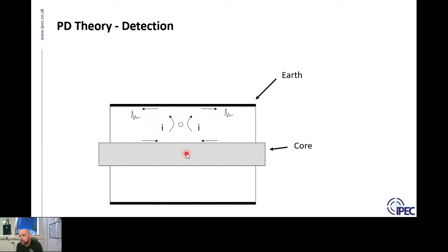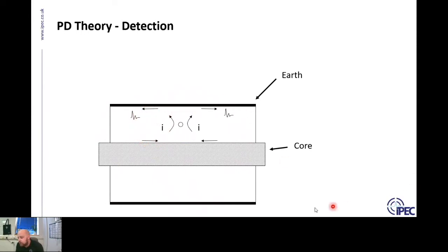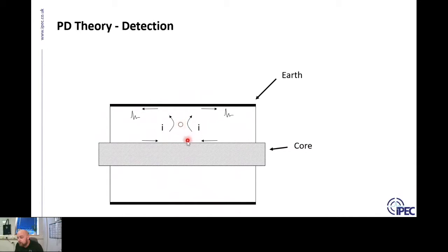High frequency signals follow their characteristic behavior within the cable. When the PD occurs, it's induced on the inside of the earth sheath and on the outside of the core. These two signals are equal and opposite — if you put any sensor around the whole cable you won't be able to detect anything. They're also trapped inside the cable, as the metal earth sheath acts as a Faraday cage, keeping the high frequency signal inside. The PD signal will travel in both directions away from the PD source, with the signal on the core being opposite to the signal on the earth sheath.